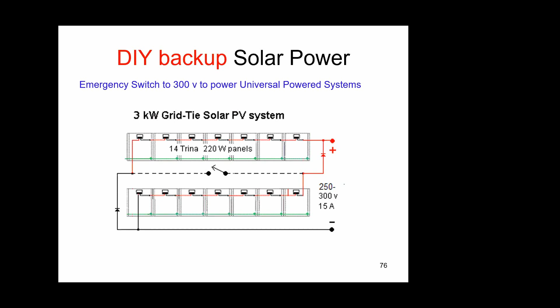How do you wire up switches at high voltage DC and high current? You can spend up to $300 for a high voltage DC switch that's UL approved — very expensive. Or what I do is use a $6 AC air conditioner disconnect box from Home Depot with a pullout, because these are rated at 60 amps, 600 volts. They're not rated for DC, but if you pull that disconnect out, you'll draw an arc — at least the arc will extinguish. That's the thing about DC switches, why they're so expensive.